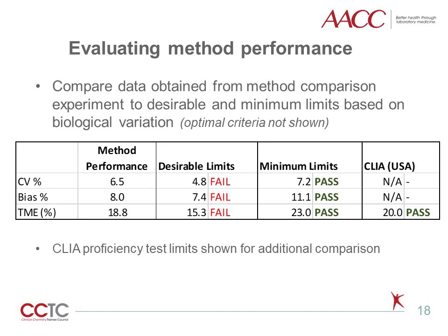By way of comparison, the error limit for ALT enzyme is plus or minus 20% based on CLIA proficiency testing in the United States. Whether such limits are greater than, less than, or equal to biological variation goals depends on the specific test analyte. Improved alignment of performance limits across clinical tests may occur if the biological variation approach is adopted by external quality assessment providers or used within the legal regulatory environment.